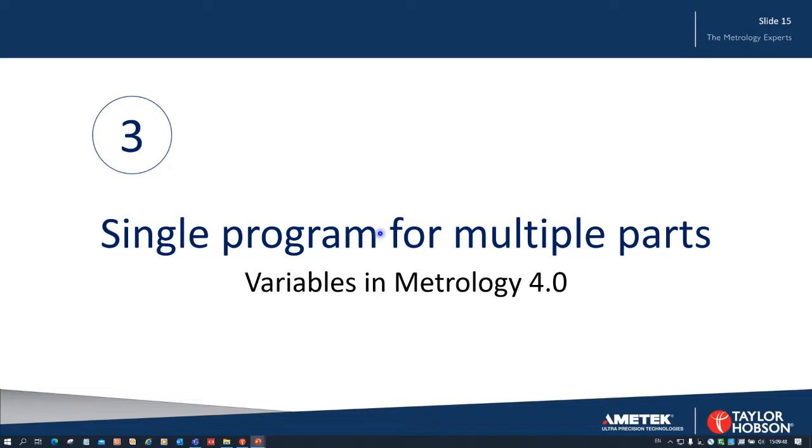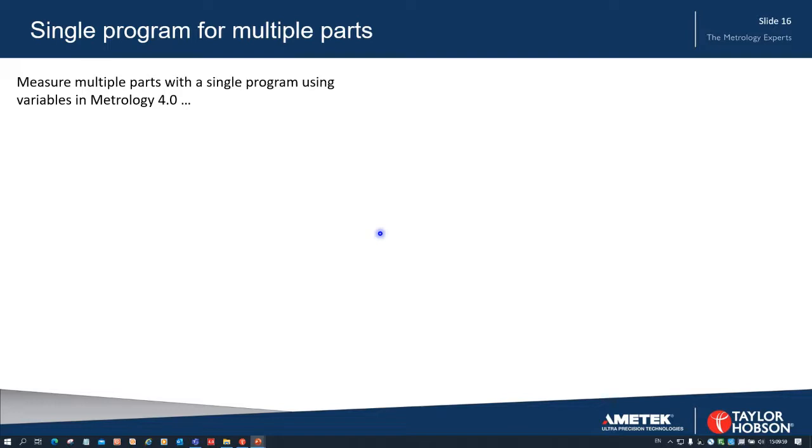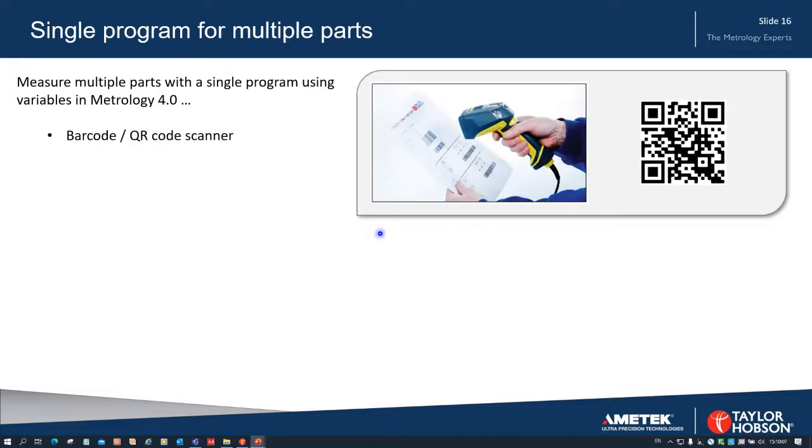That's a very important report. Let's have a look now at how in Metrology 4.0 we can measure multiple parts but just using a single measurement program. And this is done using the ability in Metrology 4.0 to use variables. So when we start the measurement we can scan with a barcode or a QR code scanner, and that will tell us which part that we want to measure, and it will call up the data about the information about the part that we're measuring from the database - from the company database or even from a text file locally on the PC.